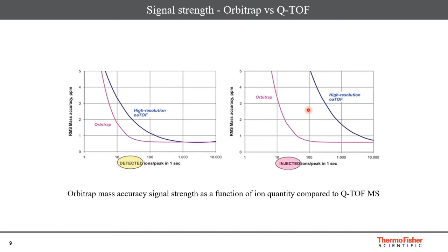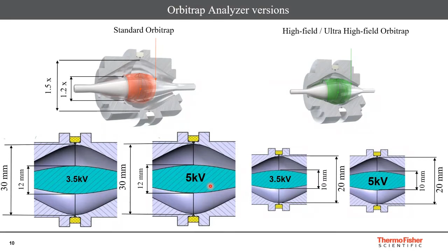So now let's go to the next slide. This particular slide gives you an overview of the different Orbitrap analyzers: the so-called standard Orbitrap in the left-hand side panel, and the high field or ultra high field Orbitrap, the one in the right-hand side panel. Essentially, they have decreased the size of the trap and increased the central electrode voltage potential from 3.5 to 5 kilovolt. All these improvements have been made so that you get better mass accuracy and faster scan speed. So that is the logic, right? In case you are interested, we can discuss these things at the end of the session.